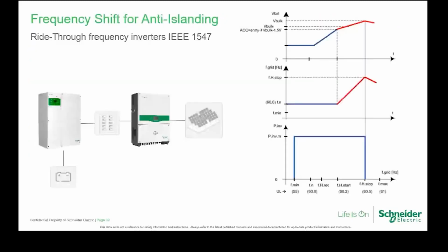So for ride-through frequency inverters, the IEEE 1547 requirement, if you look at the right-hand graph, you have the battery doing bulk and the voltage rises. The frequency will then start rising when it goes to absorption, which is the red line, because the current requirement is not as high. And then it all stops altogether when it reaches 60.5 in this case.